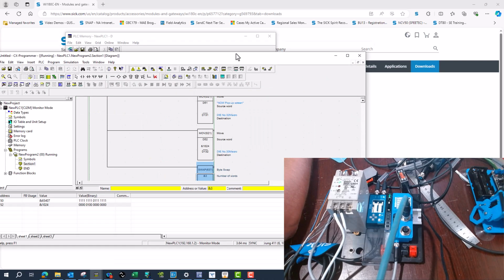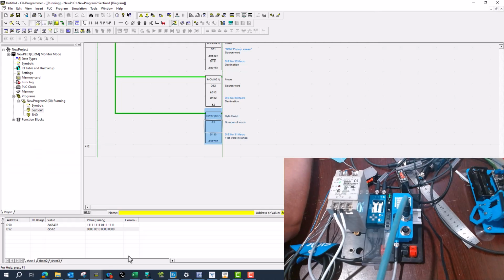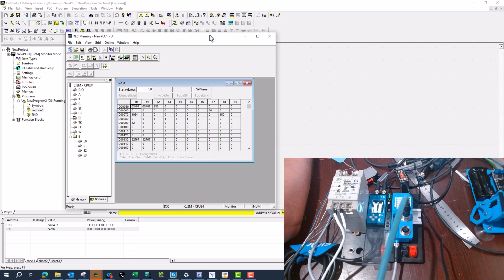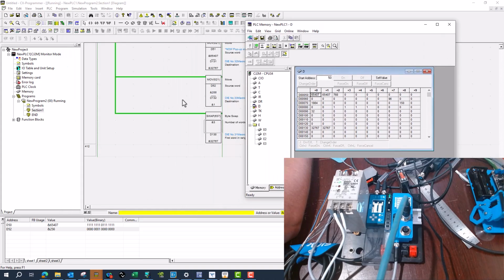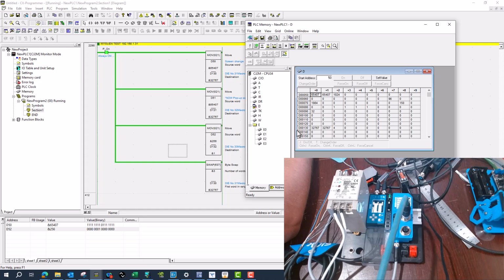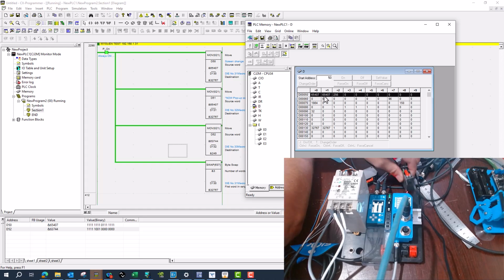And another thing that kind of threw me off is, since it's IO-Link, it's Ethernet IP straight from the device, I didn't think I was going to have to actually byte swap it like you do IO-Link data, but when you bring the data in, you can see that I'm coming in on D50 is where I had it mapped to, but that data is not any good. Right now I'm reading 33, and it's just all over the place.